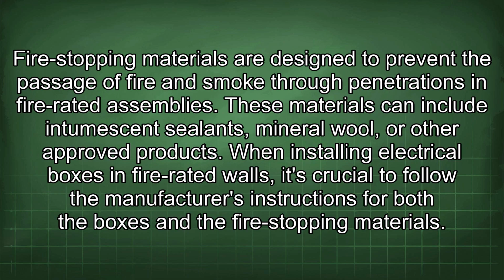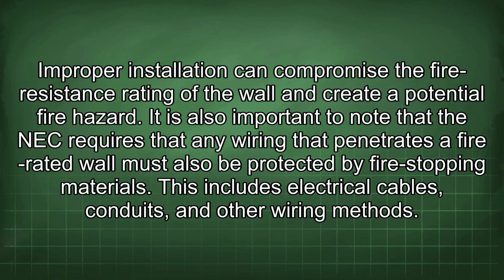Fire-stopping materials are designed to prevent the passage of fire and smoke through penetrations in fire-rated assemblies. These materials can include intumescent sealants, mineral wool, or other approved products. When installing electrical boxes in fire-rated walls, it's crucial to follow the manufacturer's instructions for both the boxes and the fire-stopping materials. Improper installation can compromise the fire resistance rating of the wall and create a potential fire hazard.